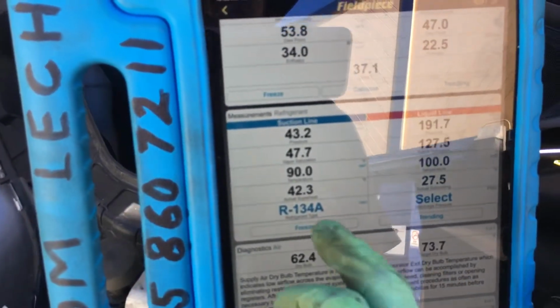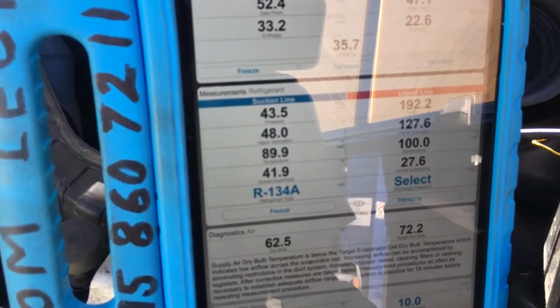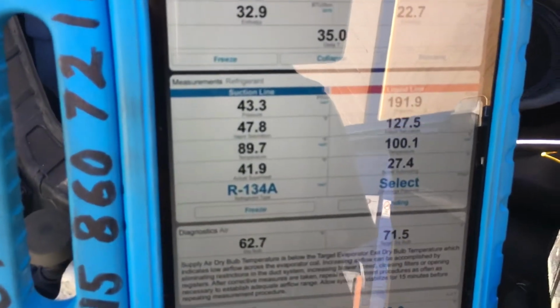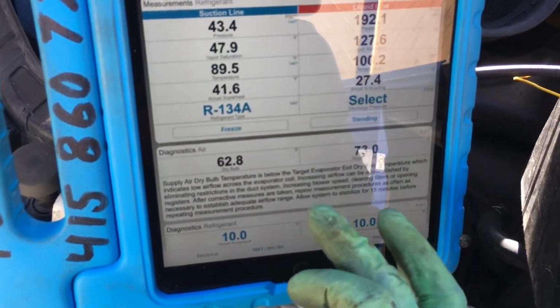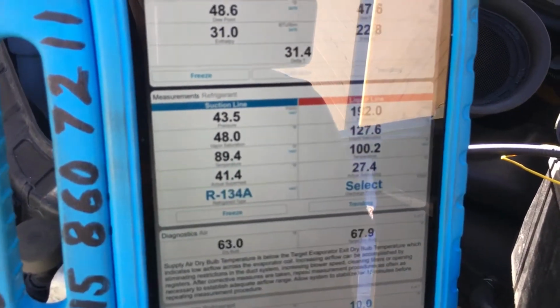Oh, well, they got a lot of insulation wrapping around that front evaporator line. Got a little section. I might be able to get this. There's like a 2-inch, 1.5-inch section I could grab onto. So now my superheat raised to 42, 41. So we'll come up. We might hit 39. But it's still very hot.